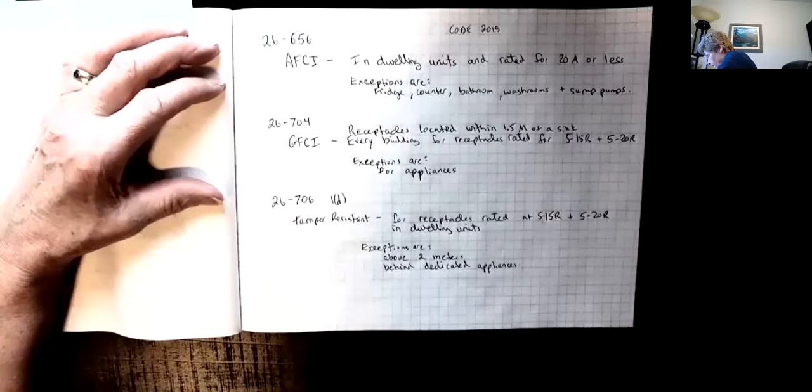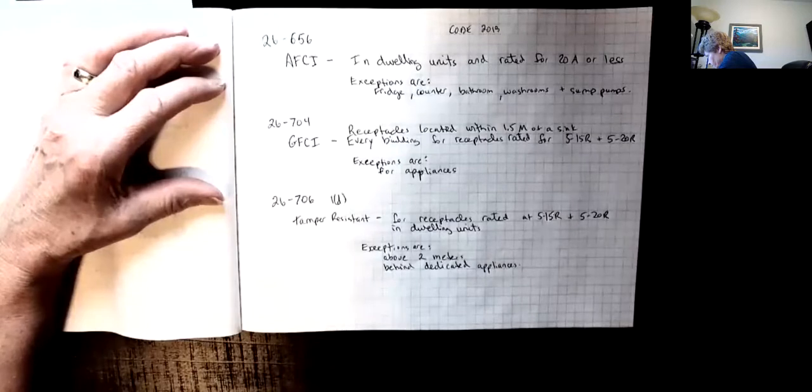26706-1D speaks to receptacles in dwelling units that must be tamper resistant and these are applied to 5-15Rs and 5-20R receptacles and the exceptions for this is receptacles that are above 2 meters or behind dedicated appliances.